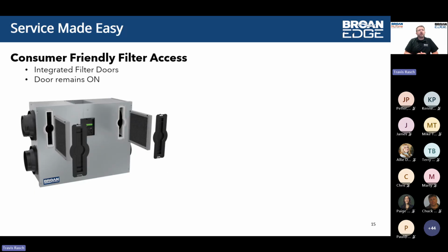Service made easy, as I highlighted on that first slide. You have those access doors integrated into the unit, so you can perform the filter maintenance on that quarterly schedule without having to take the door off, or, like our other models, swing the door open and then swing it off. There are basically locking tabs on the top and bottom of each of those access doors.